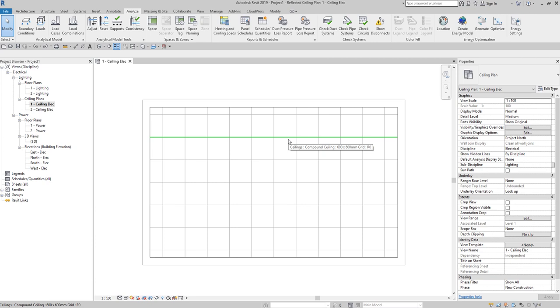Revit uses the space component to maintain information about the area where it is placed. There are values stored for the spaces — a variety of parameters that actually affect the heating and cooling loads analysis for a project. But aside from that, the space also shows some parameters that have something to do with the electrical side, like for example the average estimated illumination of a certain room. Whenever you place your electrical fixture and then click the space, you'll be able to see the average estimated illumination in the properties. But the problem is there are some instances that when you place an electrical fixture the value is zero.